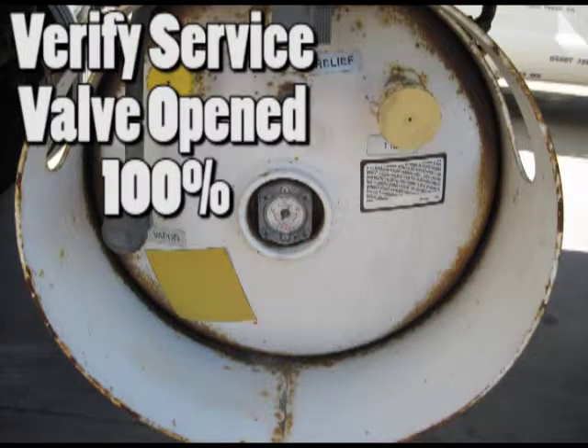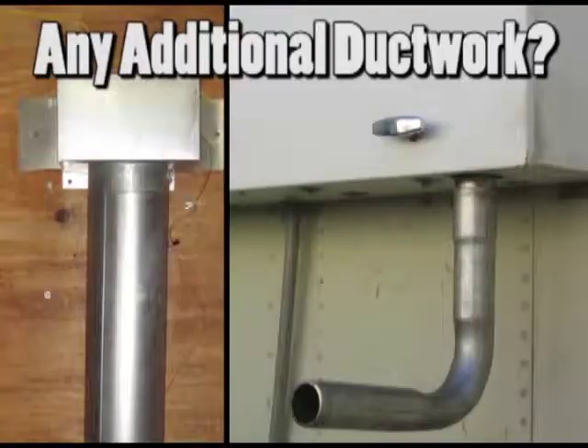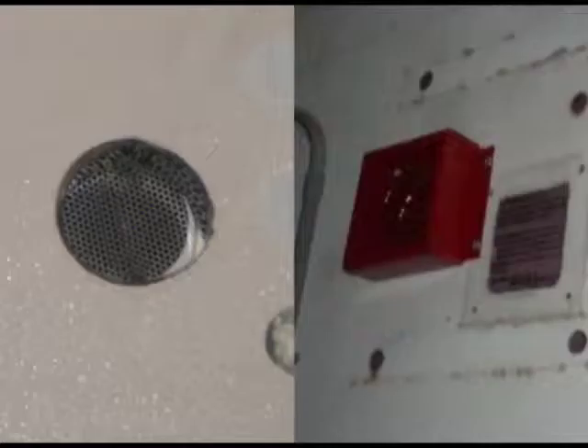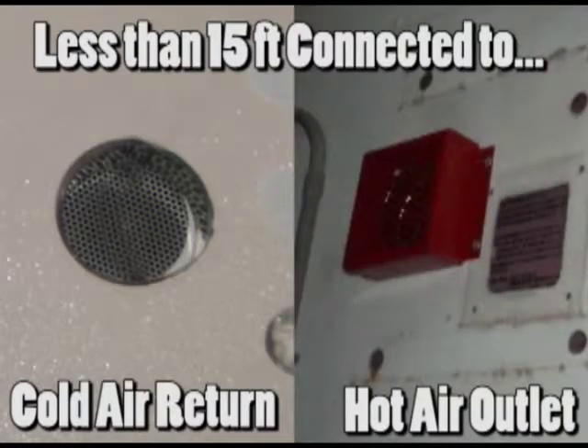Check that the service valve on the propane cylinders is fully open. Occasionally, a tank will fail to supply enough gas to the heater unless the valve is fully open. Is any extra ductwork connected to the exhaust or air inlets or outlets? If so, the heater should have less than 15 feet connected to the inlet and outlet in the trailer.